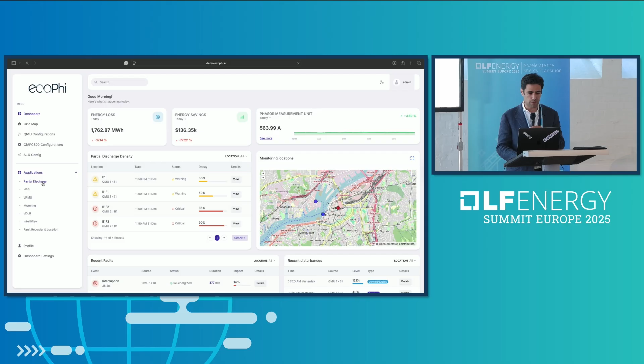Partial discharge monitoring in an online fashion without any sleep time, with a trend analysis in the substation. You can see there. And when I say no sleep time, everything is in real time. Also, at the same time, it classifies why this PD, for example, is happening, with the trend analysis and everything. So if you want to deploy online-based PD protection, the setup is already there. It's not like conventional PD monitoring where there is a sleep time: 1 second to sleep, 1 minute, 1 hour, and then continue recording.